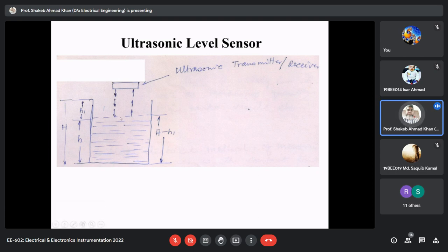Here we have an ultrasonic transmitter and detector. Ultrasonic waves are transmitted, and when they reach the liquid level, they are reflected back. Time measurement is done for how much time it takes to go to the liquid level and come back, which is called the echo. So this is basically the ultrasonic transmitter and detector pair together.